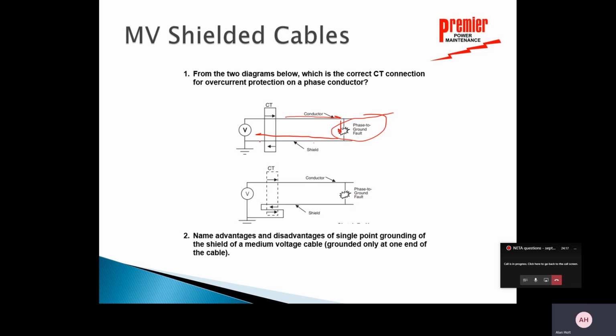And then I've got a meter here. That's not going to detect a fault because it's got the same current going in, the same current going out. That's obviously a situation that you would typically not want. Now, the next one down, the shield is coming back through the CT and into ground. So it's basically negating the current in the shield because it goes both ways through that CT. So this would be the proper connection. That would see extremely high current going to ground, but it wouldn't see it canceled out down here.